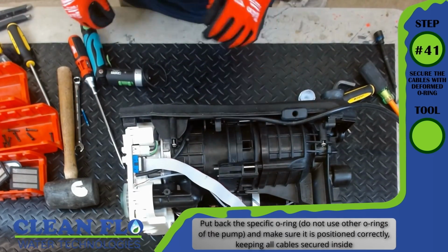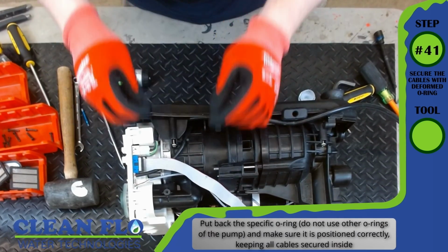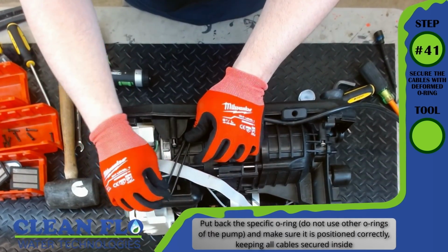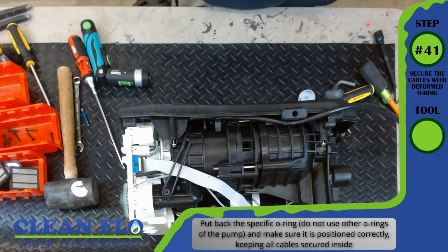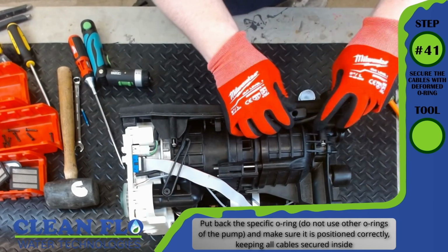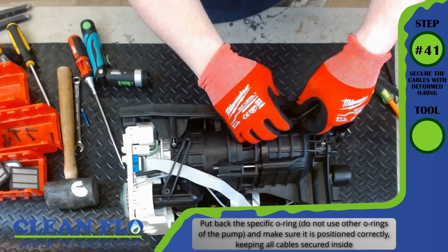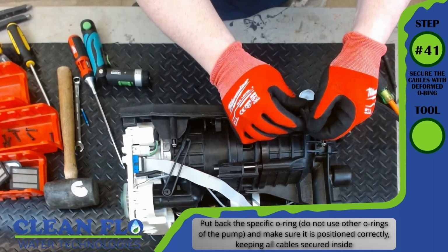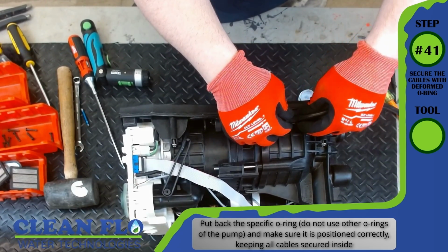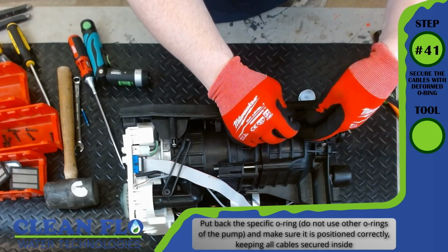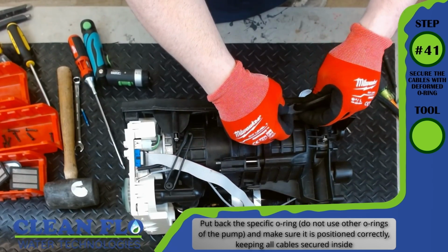Step number 41, secure the cables with the deformed O-ring. Put back the specific O-ring, do not use other O-rings of the pump, and make sure it is positioned correctly. Keep all cables secured inside. The deformed O-ring is designed to keep all the cables inside so nothing gets pinched during reassembly.